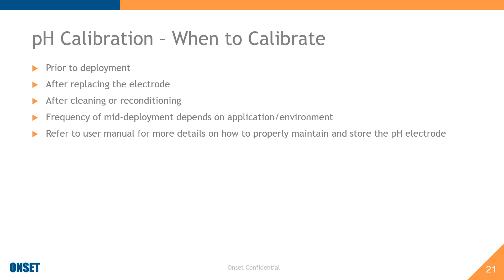You should always calibrate prior to deployment, especially with a new electrode or after long-term storage. After replacing an electrode, you'll have to calibrate. After cleaning or reconditioning the electrode, you'll want to recalibrate. During mid-deployment, the frequency of calibrations depends on the application and environment. Our Hobo Mobile and Hobo Connect software will prompt users to calibrate when first setting up a logger, and if it's been more than seven days since the last calibration, it will prompt you to calibrate — not required, but it will prompt you.